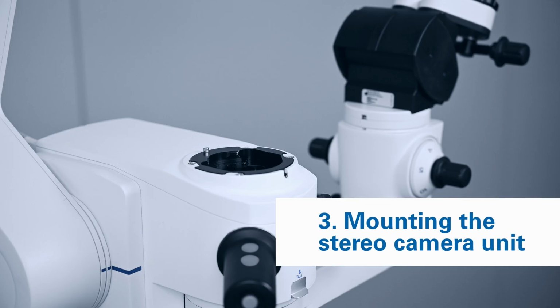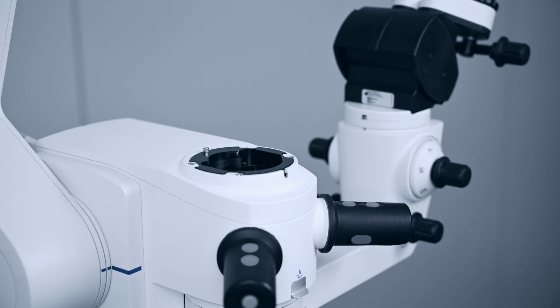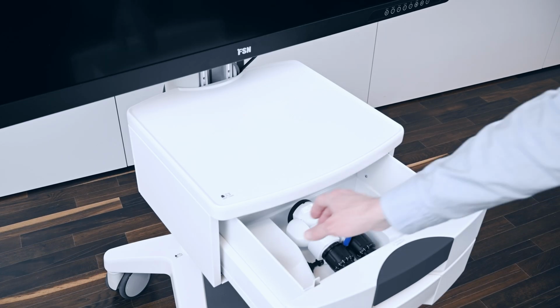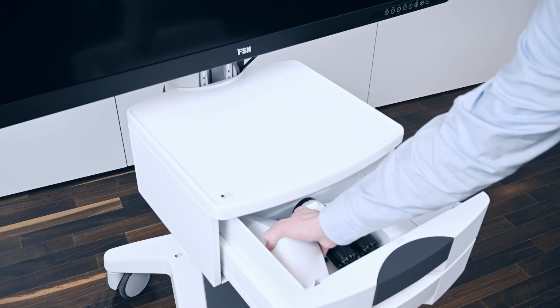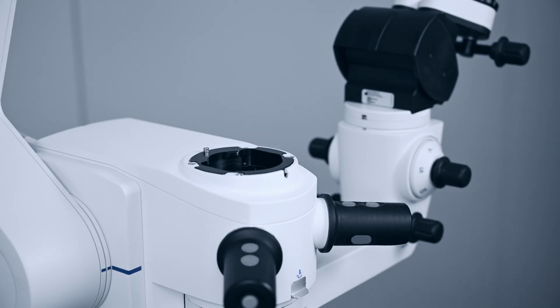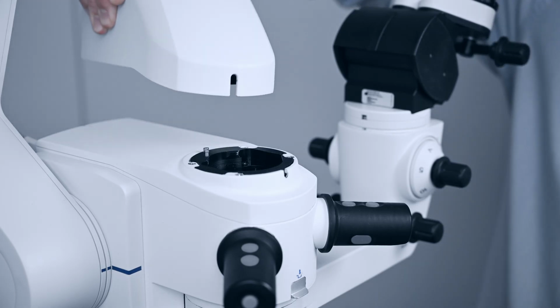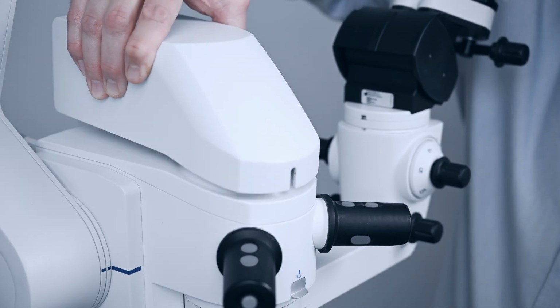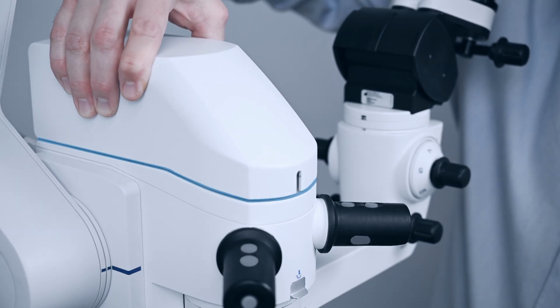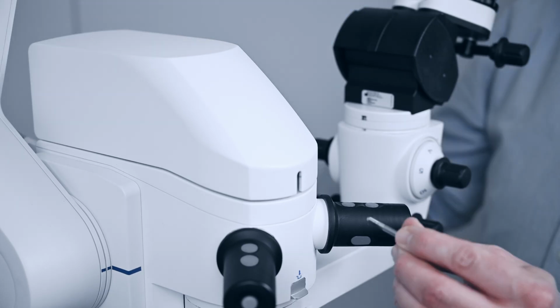Step 3. Mounting the stereo camera unit. First, take the stereo camera unit and the knurled screw from the monitor trolley drawer. Place the stereo camera unit on the dovetail connection of the microscope. Next, ensure that the edges of the stereo camera unit are aligned with the microscope. Insert the knurled screw into the hole at the front of the stereo camera unit.